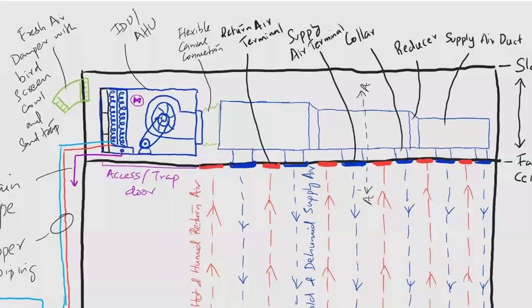So once again, guys, in this scenario the return air which comes from the room and the fresh air which comes from the atmosphere are both mixed right inside the back side of the machine, and later it is carried across the duct and rejected to the respective rooms. And again the same cycle takes place. So this is how a ductable split air conditioner works. All right, I hope it's clear.